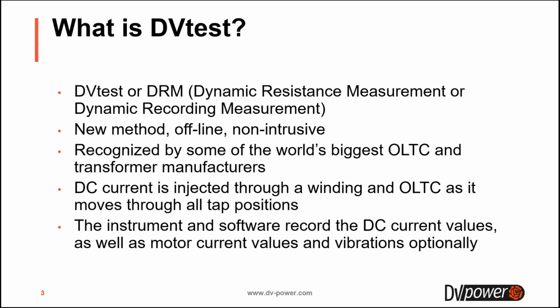It's an offline method, which means this method is testing an offline transformer, which means a transformer which is not under voltage. It is non-intrusive, which means you don't need to open the transformer, you don't need to extract the tap changer, so anything can be done on the transformer, which is completely sealed. As I mentioned, the method is not yet in the international standard, but it is already recognized by some of the world's biggest manufacturers of transformers and on-load tap changers.